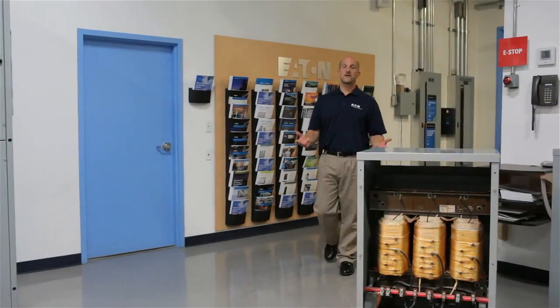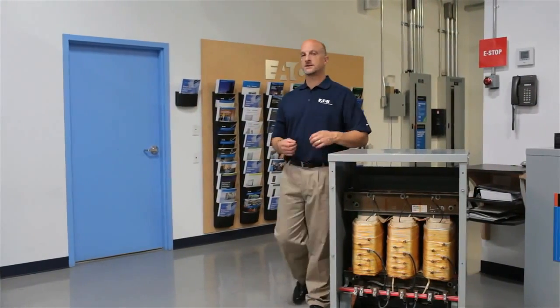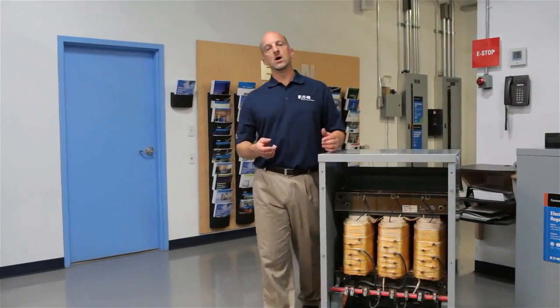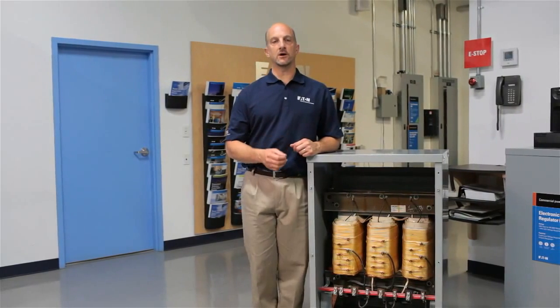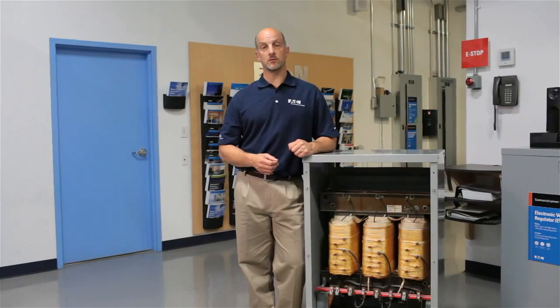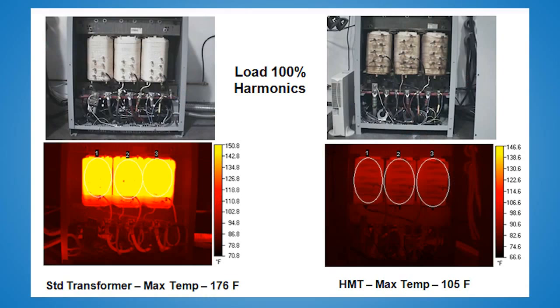The effects of harmonic distortion can appear in several ways. Overheating of equipment is a very common result of harmonics. In commercial applications, harmonic current causes the transformer's core and windings to overheat. Over time, this will progressively damage the transformer, resulting in premature failure.